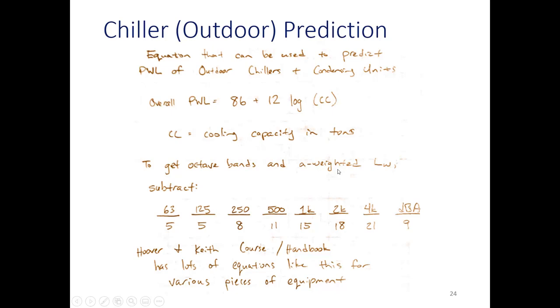To get octave bands and A-weighted sound power level, you need to subtract these values. For the overall, you just put in the cooling capacity in tons. Say it's a 10-ton unit. You put 10 in here, you get your overall sound power level, and then you subtract 5 from that to get the 63 hertz octave band, subtract 5 to get the 125 hertz octave band, subtract 8 to get 250, and so on. And for the dBA, you would subtract 9 from whatever you get here. Like I said, this is from Hoover and Keith. It's a handbook for a course that they taught.